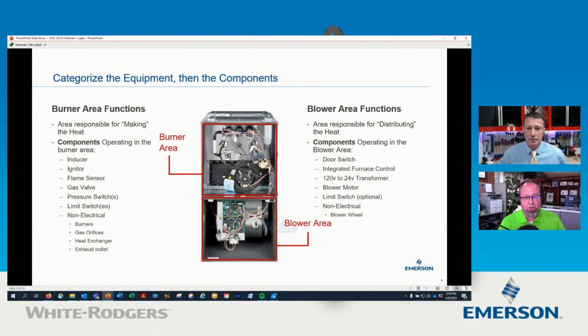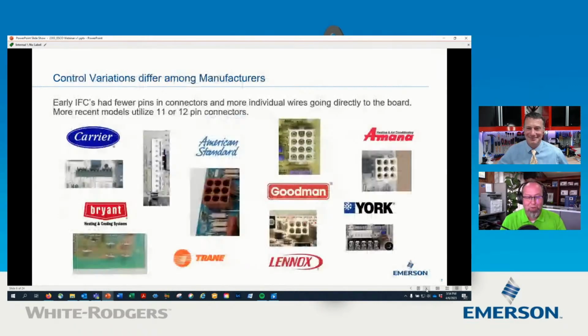Now that you know it's not coming on with your senses, you get to pull the meter out, after you've determined this isn't part of the sequence functioning the way it should. Sure. And from that, you can start using your meter to see, hey, is it getting 120 volts to the speed that's supposed to be running right now? Sure. So again, it's about understanding these are the functions, these are where they're located, and this is the whole picture. There's nothing else. I'm trying to make this as simple as possible to understand where we're at.